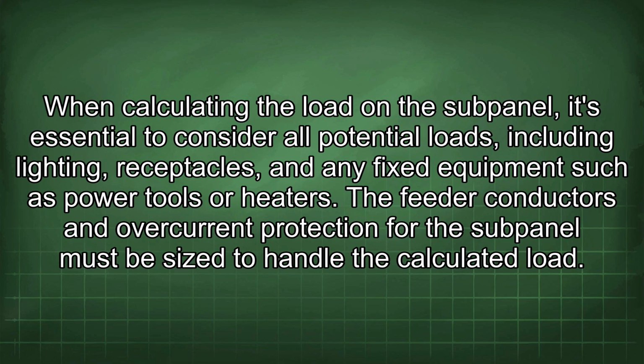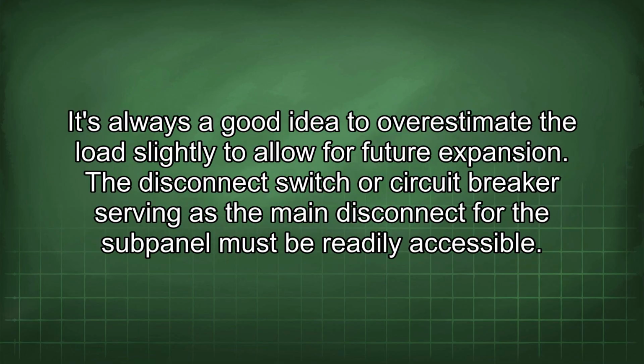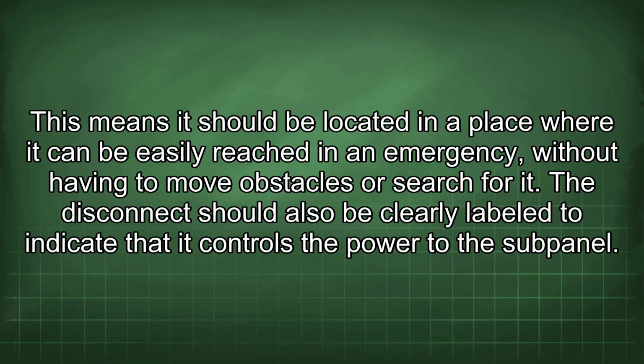When calculating the load on the subpanel, it's essential to consider all potential loads, including lighting, receptacles, and any fixed equipment such as power tools or heaters. The feeder conductors and overcurrent protection for the subpanel must be sized to handle the calculated load. It's always a good idea to overestimate the load slightly to allow for future expansion. The disconnect switch or circuit breaker serving as the main disconnect for the subpanel must be readily accessible. This means it should be located in a place where it can be easily reached in an emergency without having to move obstacles or search for it.